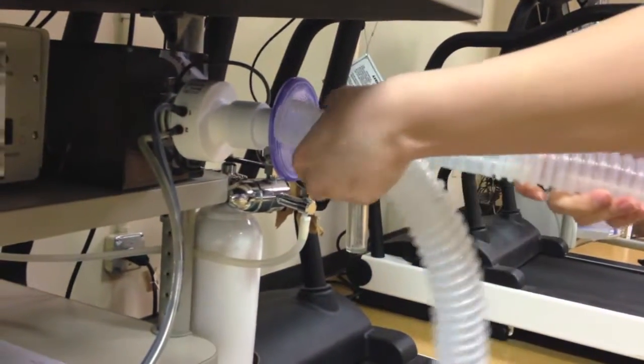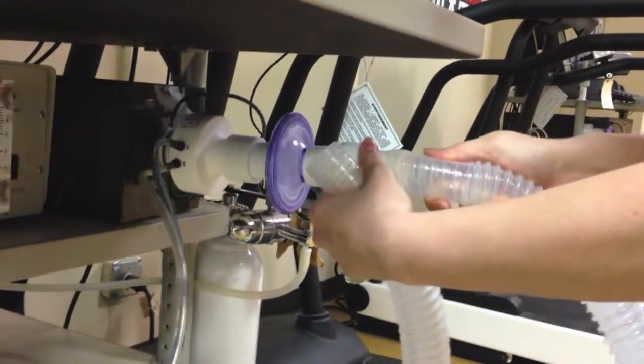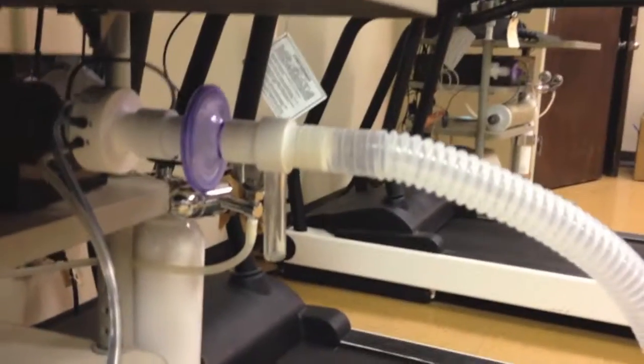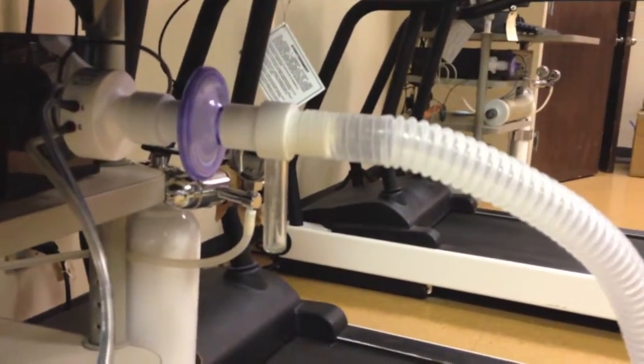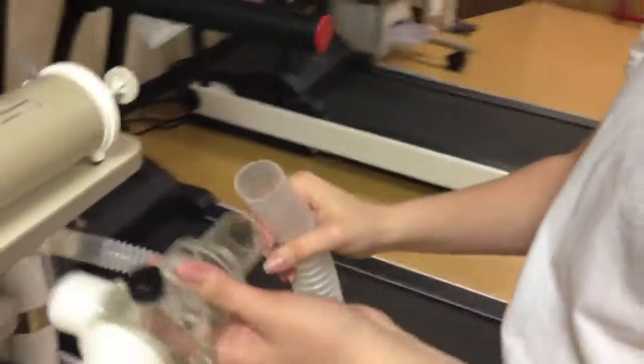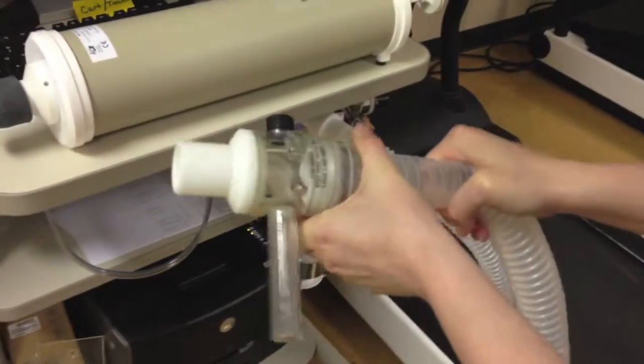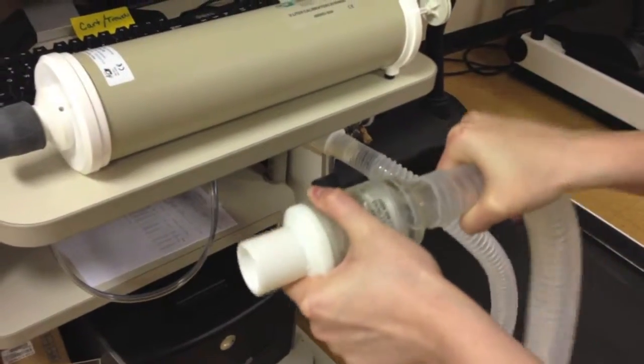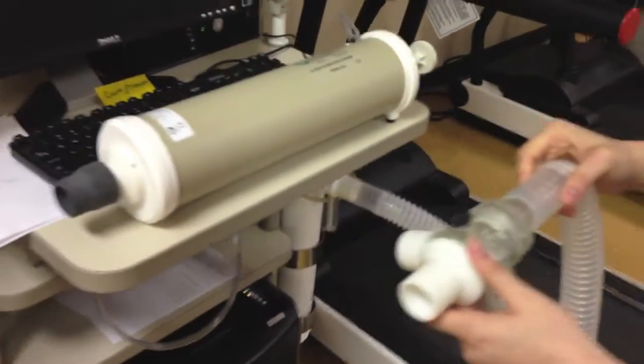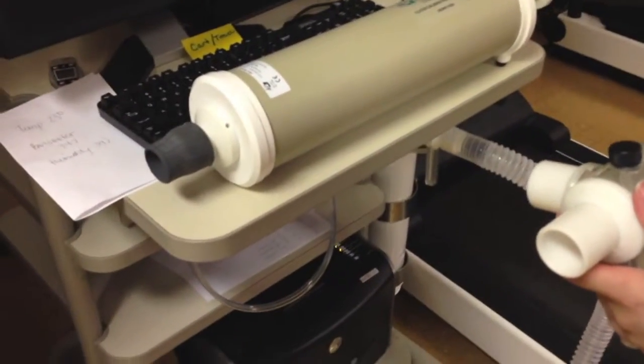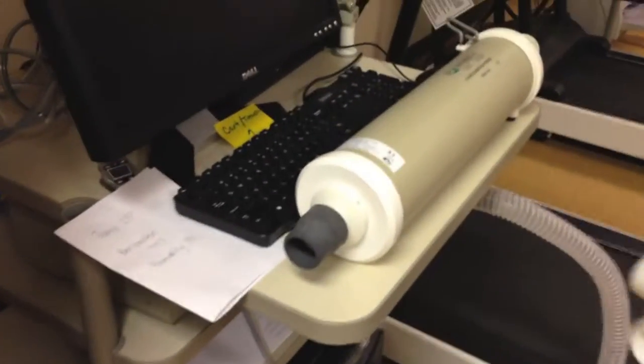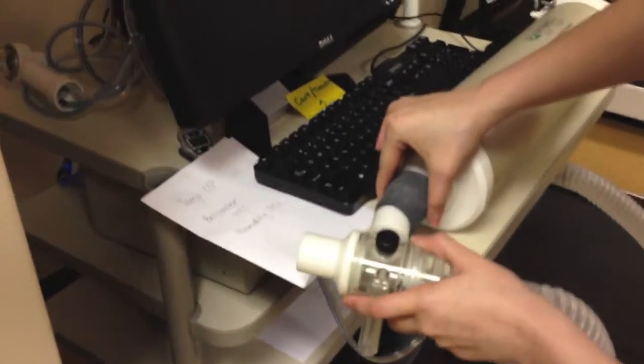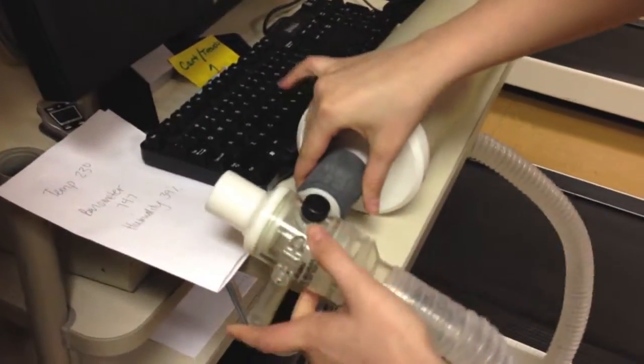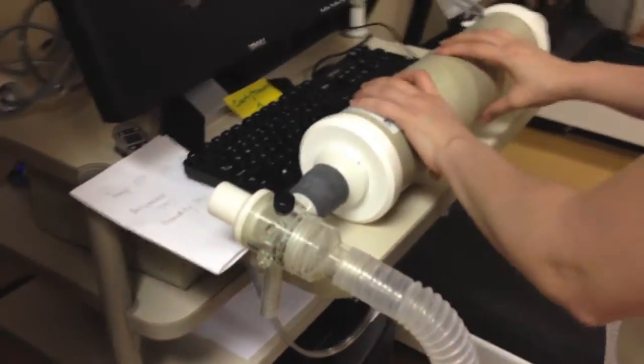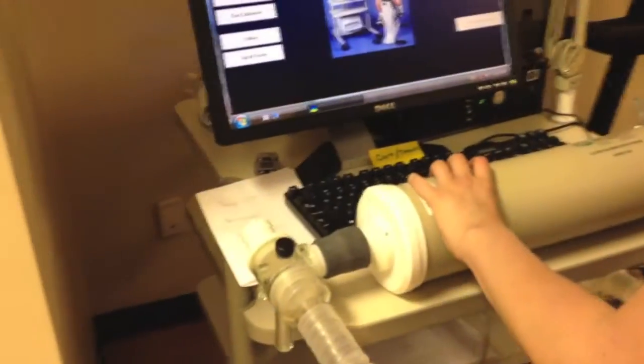as shown here. Once all that is connected, you will take the other end of the tube and connect it clear to clear to the two-way breathing valve, as shown. Make sure that this is tight and secure. To calibrate the flow sensor, we will then plug the breathing valve to a certified 3-liter calibration syringe, which is used to push air through the system, simulating the breathing pattern of an adult. After everything is connected and secure, you will then press the flow meter calibration on the computer.